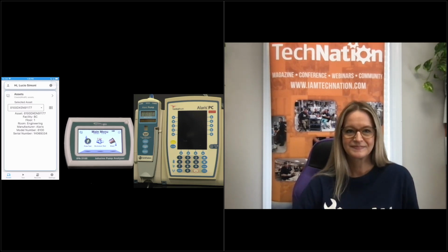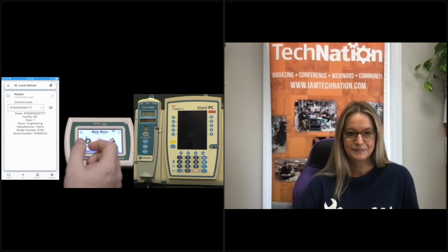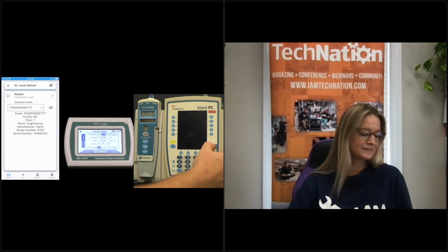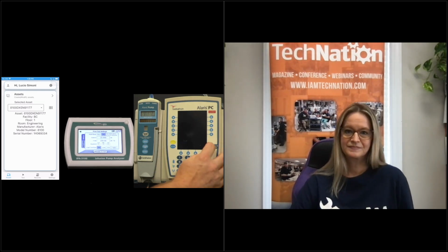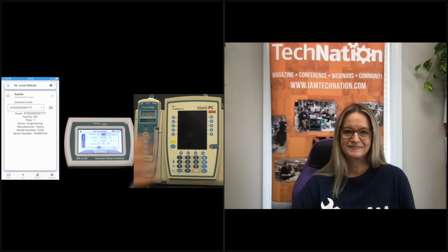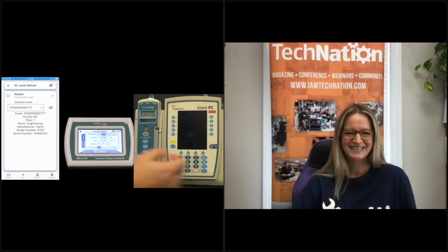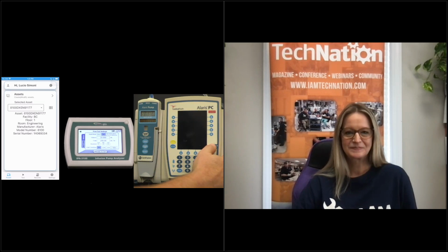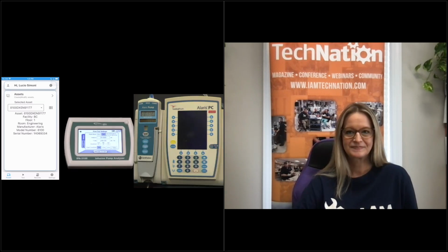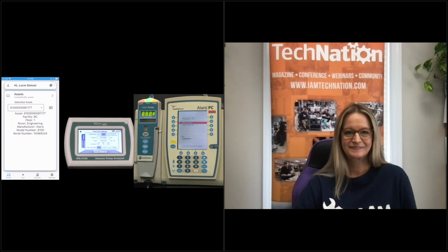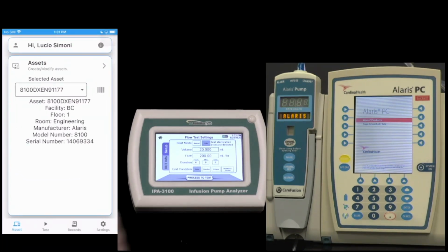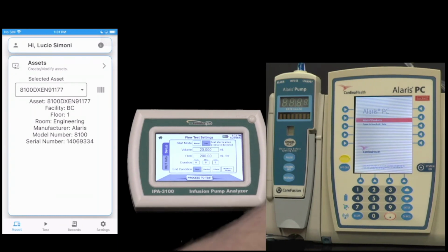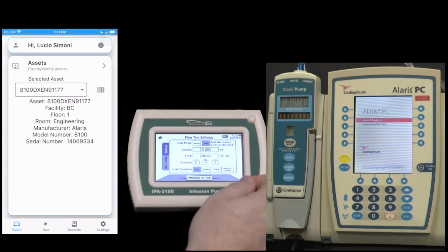So if we go back to our flow test, I'm going to go into a flow test here. I'm going to turn on the pump. First I can answer the question: no, bubbles don't affect the IPA-3100. I'm sure you've been in the middle of a test, running 20 minutes or an hour or 24 hours. Obviously the pump will throw an alarm if it sees an air bubble.